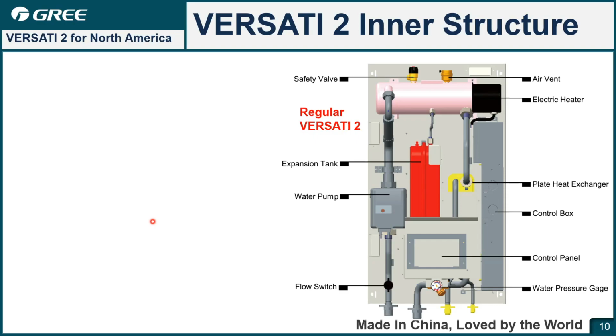And another part for the VERSATI 2 for North America. First we have a look at the regular VERSATI 2 for the European market and the other markets. If you open the panel of the hydro box, then you can see the inner structure of the VERSATI 2. Sorry, we start from the right. Here is the water pressure gauge. You can see this one detects the water pressure inside. Here is the control panel built in. And here is the control box for the wiring connection. Here is the plate heat exchanger to get the hot water. And this is the e-heater.